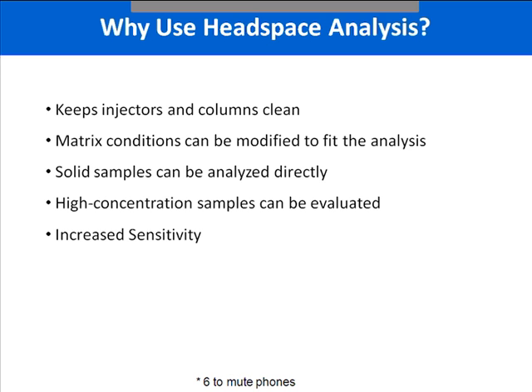This chemistry in a vial is very useful to selectively adjust response factors. Solid samples are often difficult to analyze because they can't be directly injected into the GC; prior solvent extraction is a typical technique. This leads to high detection limits due to the small amount of extract which ultimately is injected. Samples that have high concentrations of analytes of interest may be analyzed without fear of carryover, as the injector sees only a gas phase sample. The headspace system is heated to prevent absorption, which often is the cause for carryover.